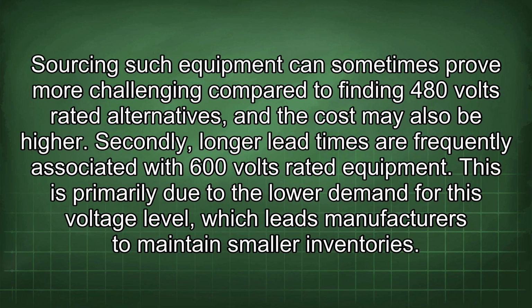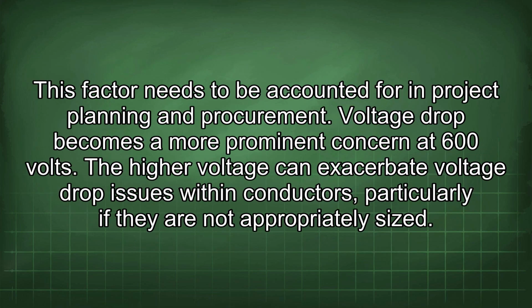Sourcing such equipment can sometimes prove more challenging compared to finding 480 volts rated alternatives, and the cost may also be higher. Secondly, longer lead times are frequently associated with 600 volts rated equipment. This is primarily due to the lower demand for this voltage level, which leads manufacturers to maintain smaller inventories. This factor needs to be accounted for in project planning and procurement.